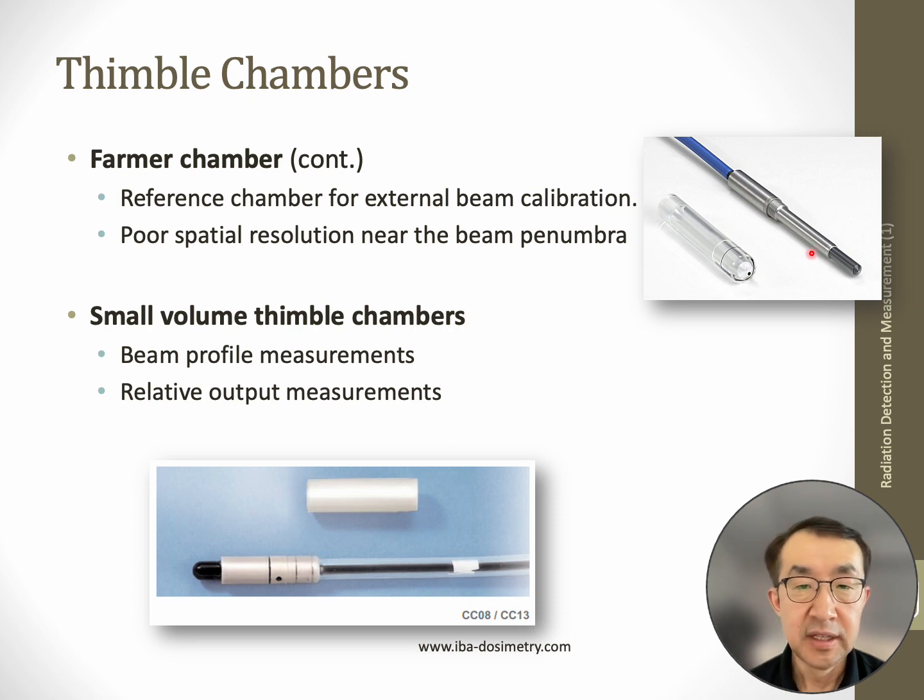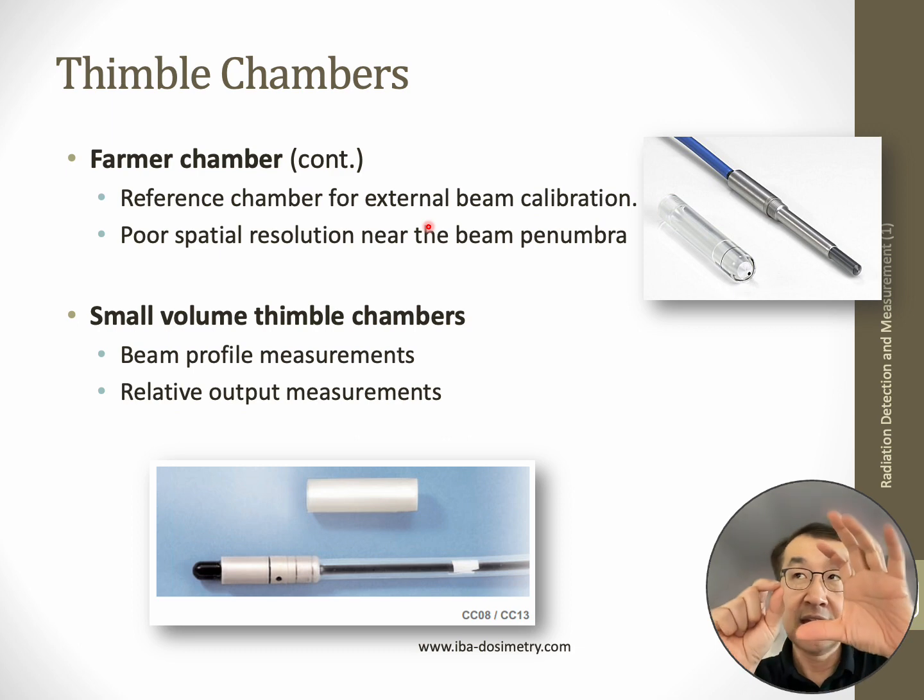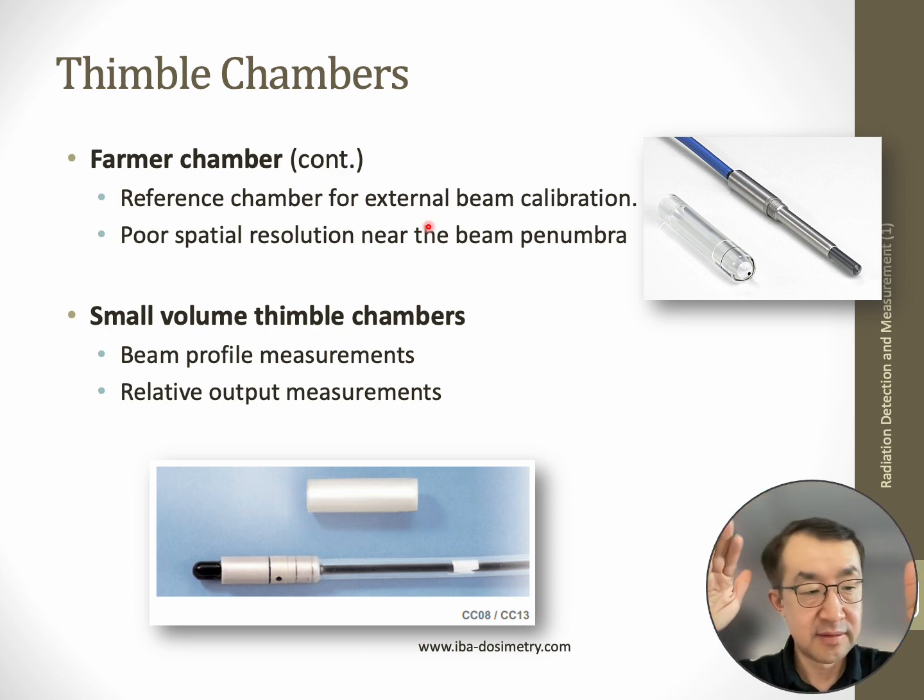However, we cannot accurately use this Farmer type chamber for beam profile measurement, because it is too big. It is good for point dose measurement at a standard setup at depth, but it is never designed for profile measurement or depth dose measurement. So big no. Farmer chamber is not good for PDD measurement because it's too big.